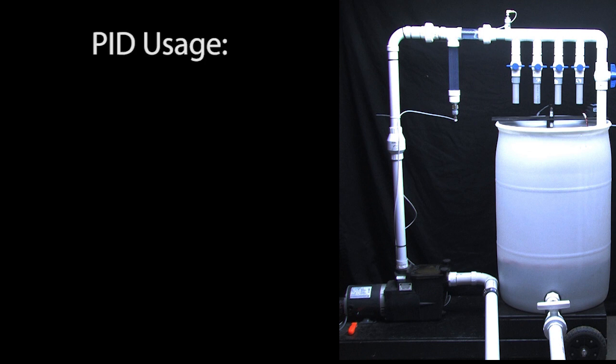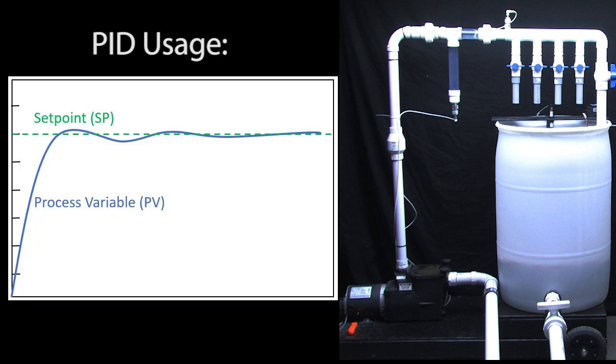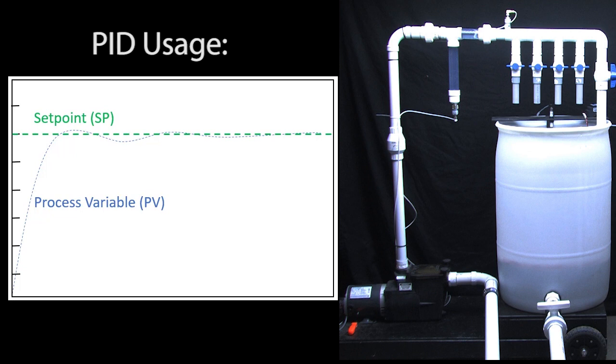Now keep in mind this isn't really your typical PID thing is it? Normally PID is used to get a process to some level and automatically hold that level regardless of load. We're not doing that. Instead, we're just going to leverage the PID function to automatically control how the motor operates while it's filling the tank.